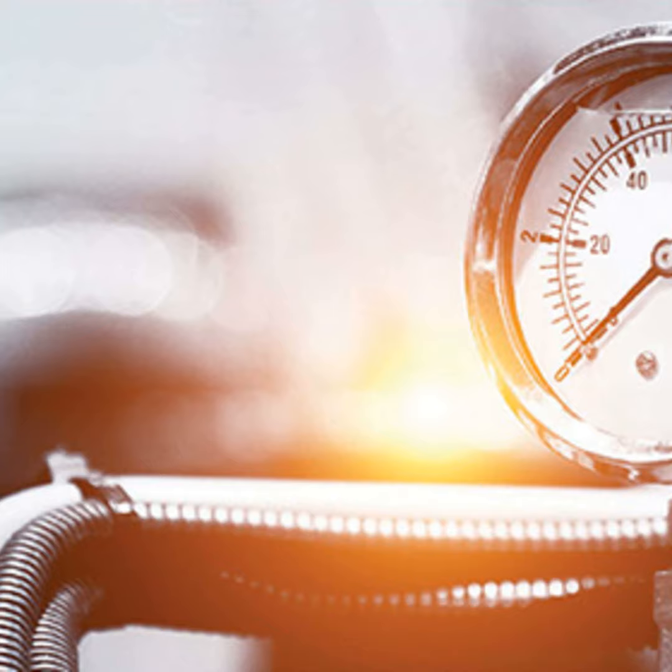Having said that, the running costs of them are a little bit better. They're substantially better actually than the electrical system. But to justify the investment, you'd want to be using a lot of hot water, like 200 or 300 litres per day, to sort of warrant it. That oil-fired one, that's really high usage. You'd want something other than just basic farm usage from that one. Yeah, I mean, where you see them going in now would be in the rotary milking part, for example, where you're washing 40, 50 units in a milking machine, things like that.